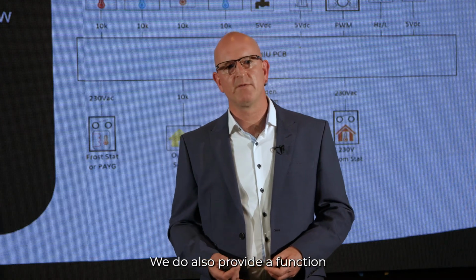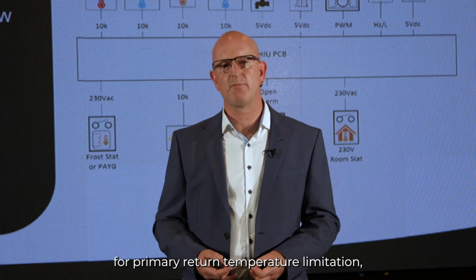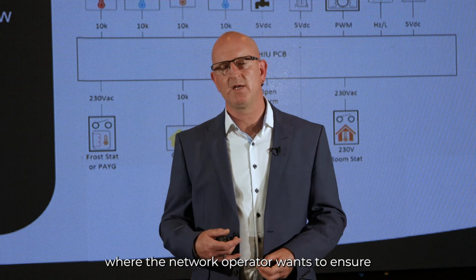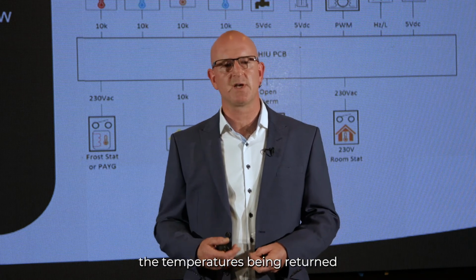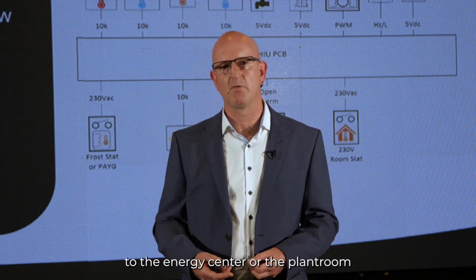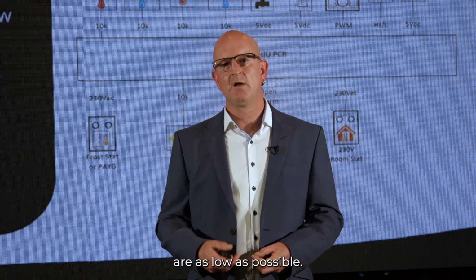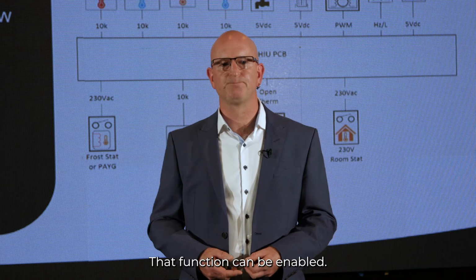We do also provide a function for primary return temperature limitation, where the network operator wants to ensure that temperatures being returned to the energy centre or the plant room are as low as possible. That function can be enabled.